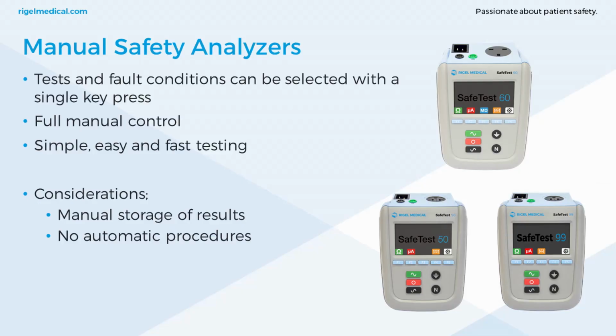I've gone over our automatic safety analyzer today, but there are other options available from Rigel if you don't feel that the automatic safety analyzer is for you. We also have the Safe Test range. Now, Safe Test 50 and 99 are specific to the US market, so that's geared more towards NFPA 99, but they have simple, easy to use and fast testing, and it's that single key press for selecting fault conditions, carrying out tests, which can be beneficial to some engineers.